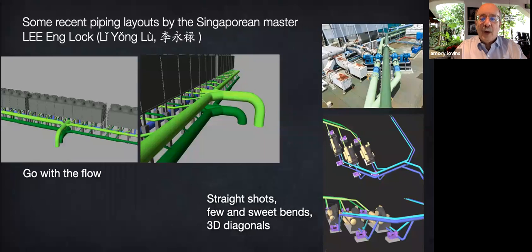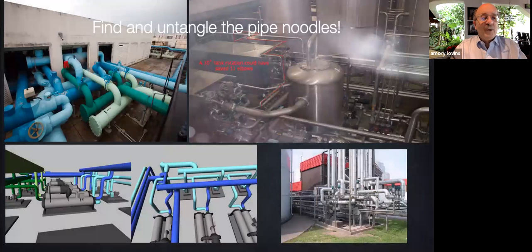At the upper right, the green pipes and blue pumps were added to older equipment. The pumps are oriented diagonally where they need to go, not at the customary right angles. The computer drawings below that photo show how three chillers, the tan things that are not visible in the photo above, were not aligned in a neat row, but were staggered just the right amount so diagonal pipes on both ends could minimize bends. If there were more room, the chillers could even splay out at different angles, each straightening the piping a bit more. Sometimes equipment could even be advantageously tipped out of its normal vertical orientation if its design allows. Of course, very few designers think this way.